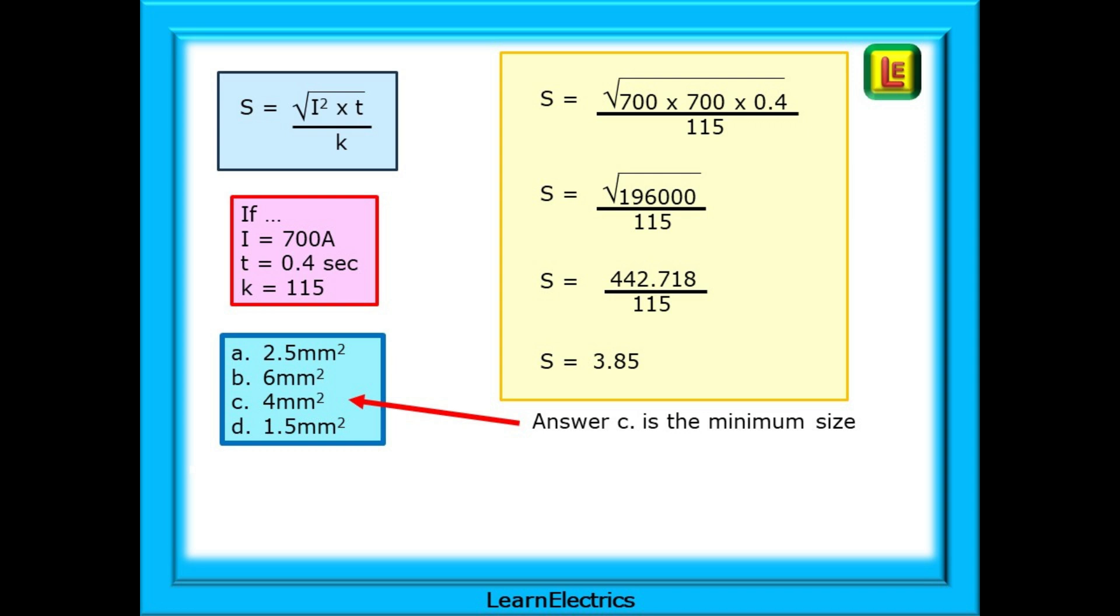We will use the formula unchanged. Follow the working out in the yellow box. Work everything out that's beneath the square root first. Now we have the square root of 196,000. Square root this and the calculation is now 442.718 divided by 115 and the answer, the minimum size for the earth conductor is 3.85 square millimeters. As this is the minimum size we should choose the nearest size that is equal to or greater than 3.85 which is 4 square millimeter conductor. Answer C. So easy if you follow a methodical approach.